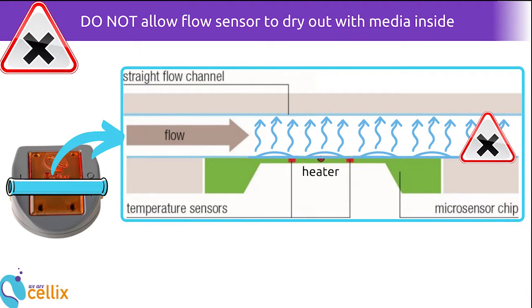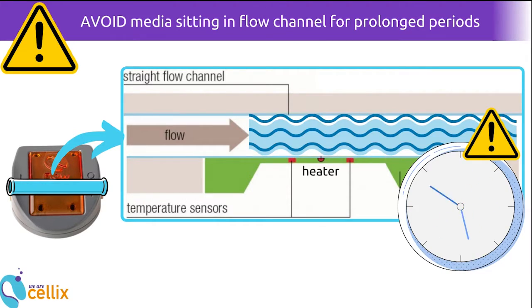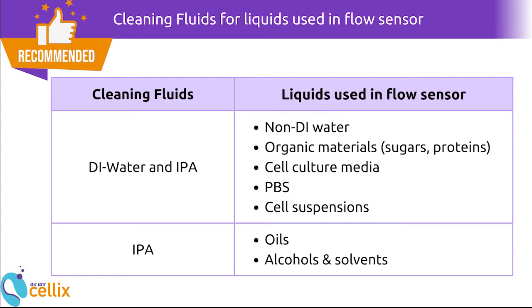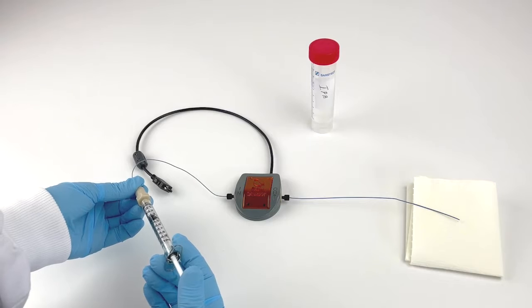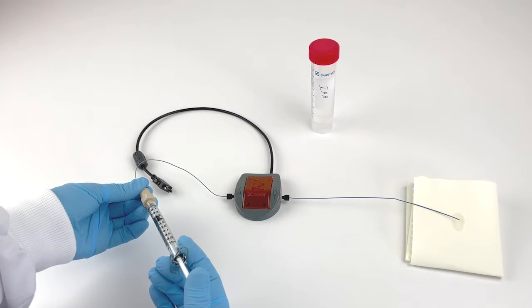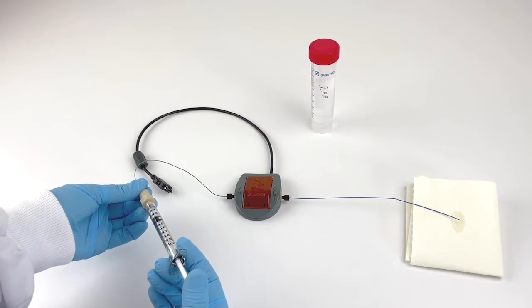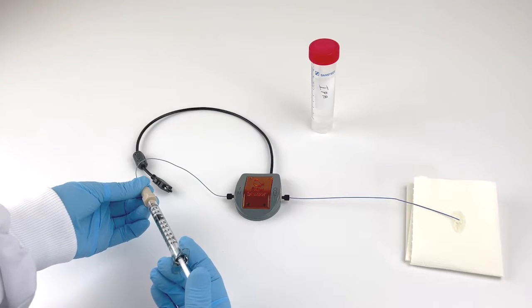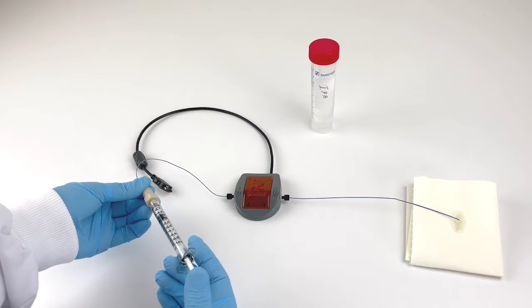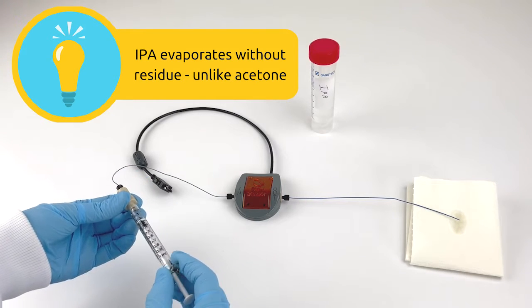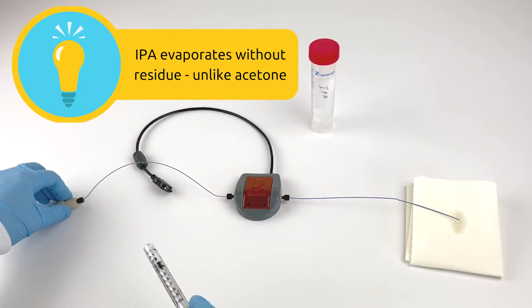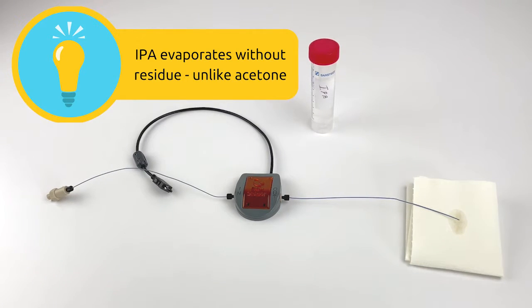General rules. Do not allow the flow sensor to dry out with residual media inside the flow channel. Avoid letting a filled flow sensor sit for prolonged periods. Cleaning agents should be chosen for their effectiveness in removing the liquid media. In general, we recommend finishing the cleaning procedure with an isopropyl alcohol, or IPA, flush before draining the fluid and closing it for storage. Top tip. The advantage of using IPA is that it evaporates without residue, in contrast to acetone.